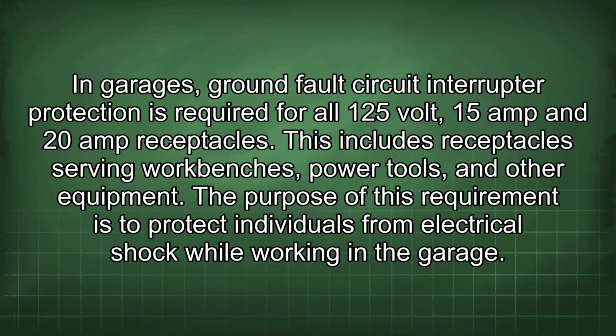In garages, ground fault circuit interrupter protection is required for all 125 volt, 15 amp and 20 amp receptacles. This includes receptacles serving workbenches, power tools, and other equipment. The purpose of this requirement is to protect individuals from electrical shock while working in the garage.